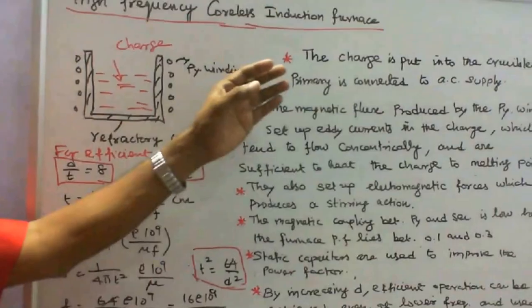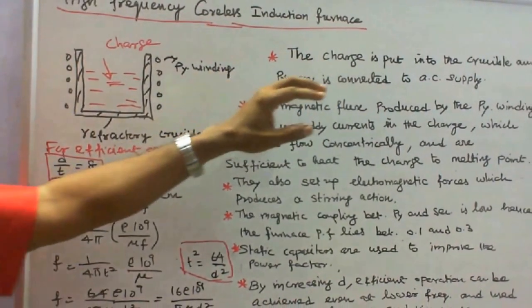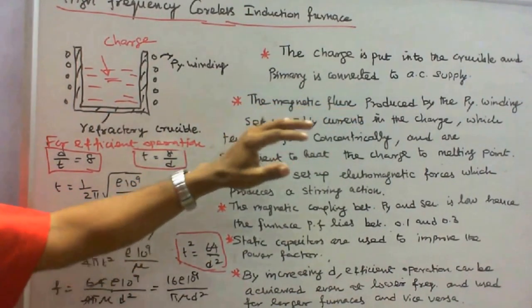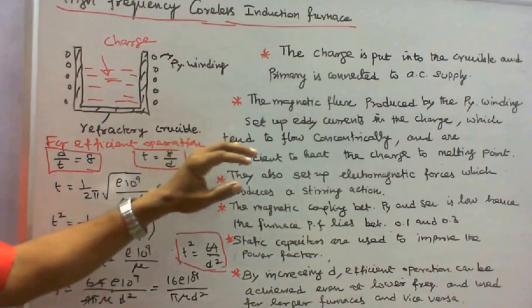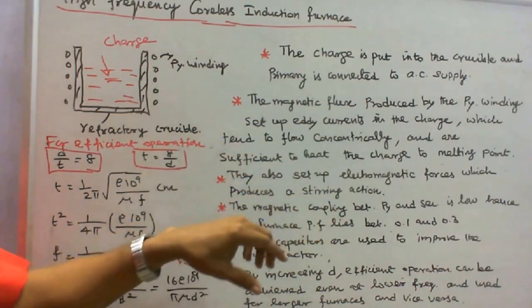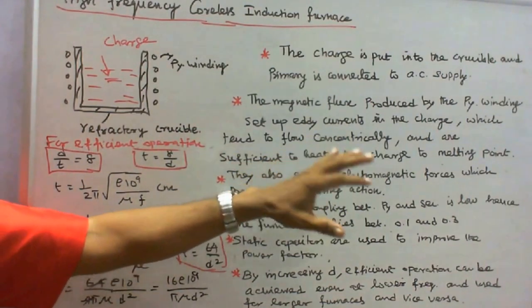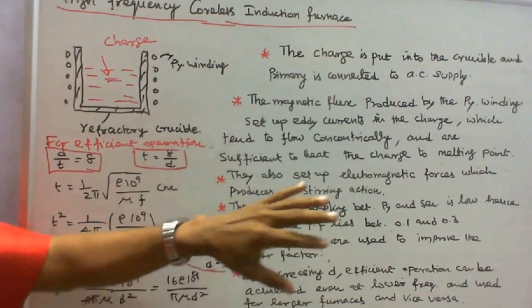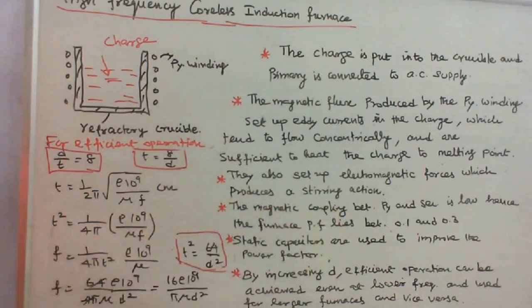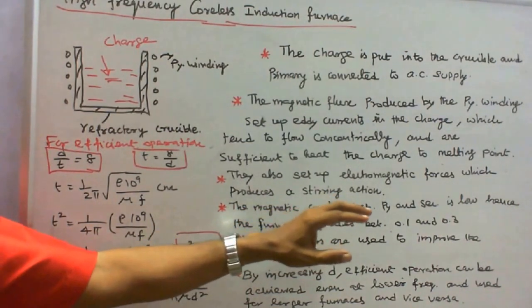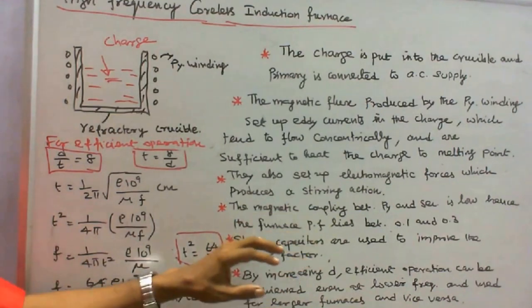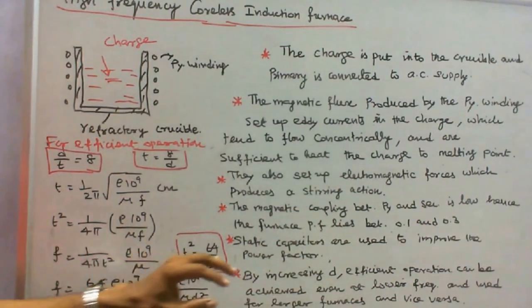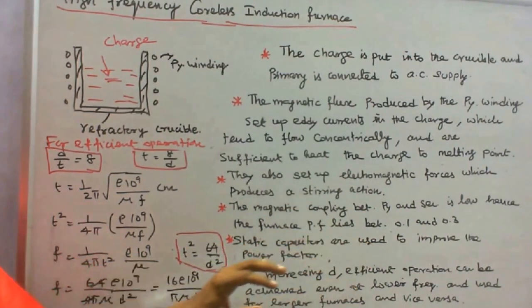The charge is put into the crucible and the primary is connected to AC supply. The magnetic flux produced by the primary winding sets up eddy currents in the charge, which tend to flow concentrically and are sufficient to heat the charge to melting point. They also set up electromagnetic forces which produce a stirring action. The magnetic coupling between primary and secondary winding is low, and hence the furnace power factor lies between 0.1 and 0.3.